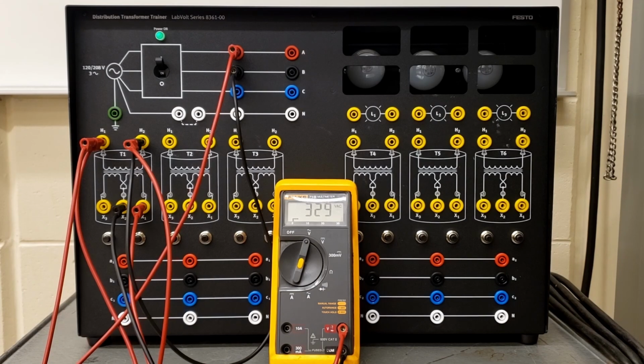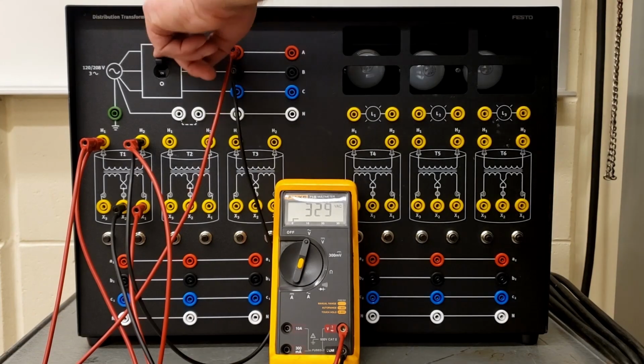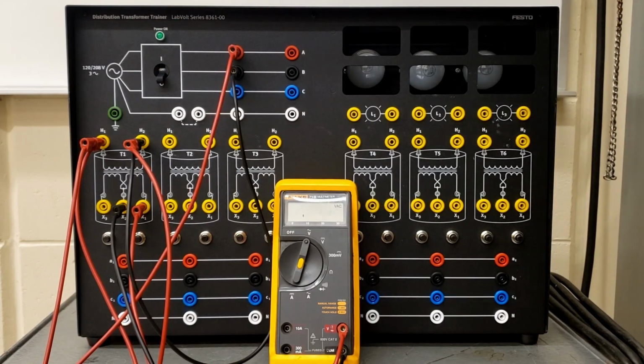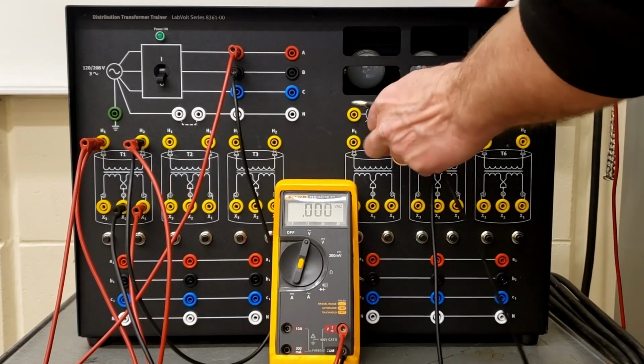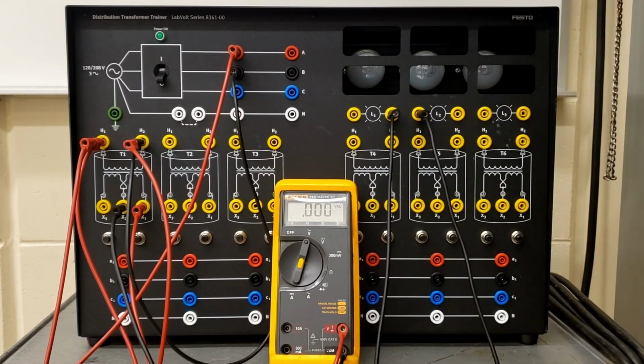It's supposed to give us 328, but we're seeing 329 on the meter. Then they want us to connect that across the bulbs. We've got to put the bulbs in series, so let's turn this off. The bulbs are rated for 230, and we just saw a voltage of 328, so we've got to put 2 bulbs in series here, then connect between those 2 points.